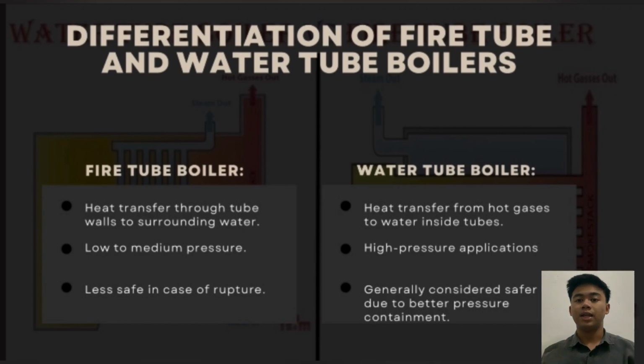So the next differentiation between water tube boiler and fire tube boiler is safety. Fire tube boilers, with their larger water volume, are proportionally less safe in the event of a rupture. Water tube boilers are generally considered safe due to the smaller quantity of water and the ability to contain high pressure steam effectively.